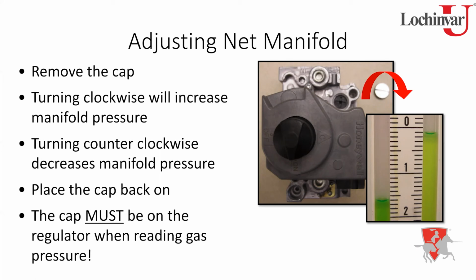And it's like any other regulator. If you do need to make an adjustment, you turn it clockwise to give you more pressure, because you're pressing down on that diaphragm, and counterclockwise to give you less pressure. Don't go nuts with it. Just make a small adjustment, see where you're at, because typically they're not going to be that far off. You're not going to see that much movement in it.